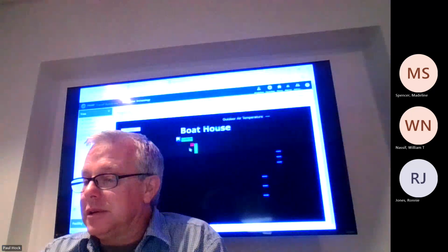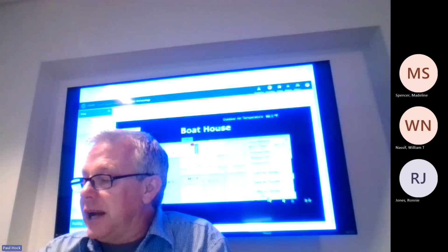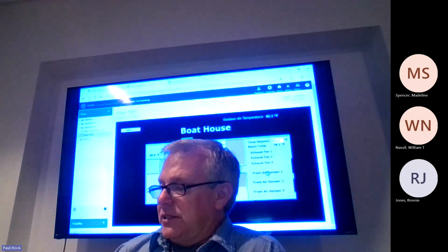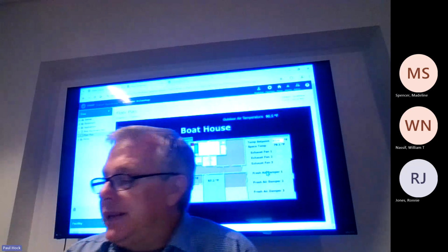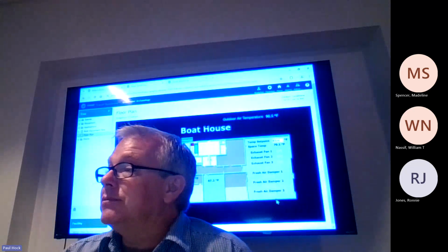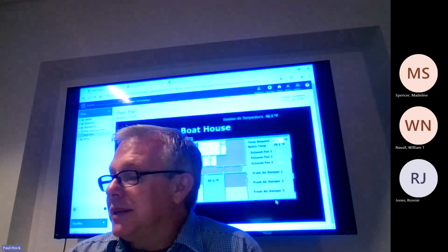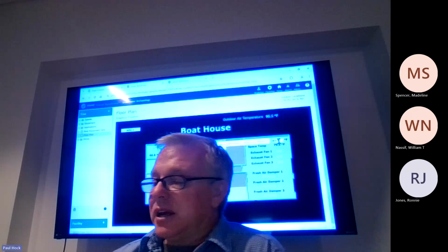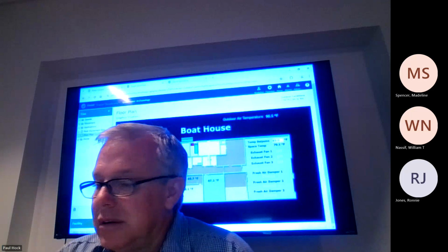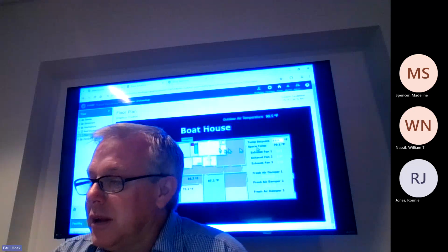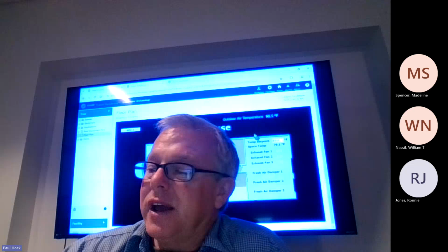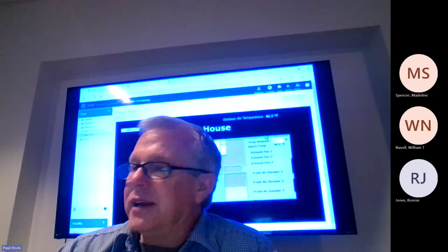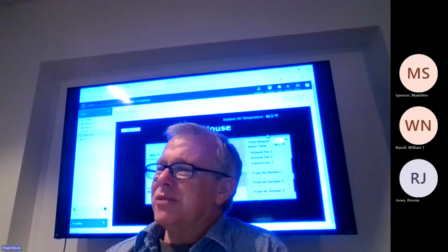Let's go back to the phone there. This is for the actual lodge. There are 3 exhaust fans and 3 dampers. Once the exhaust fans kick on, there should be dampers on this side of the building that open up just to draw some air in. Space set point is set for 85. I don't think I have an override on there. You just put an exhaust fan override button on this one, boathouse for me, and I'll get that installed. That way you guys can kick the exhaust fans on if you want. I don't know if they start their boats up in that garage or not.